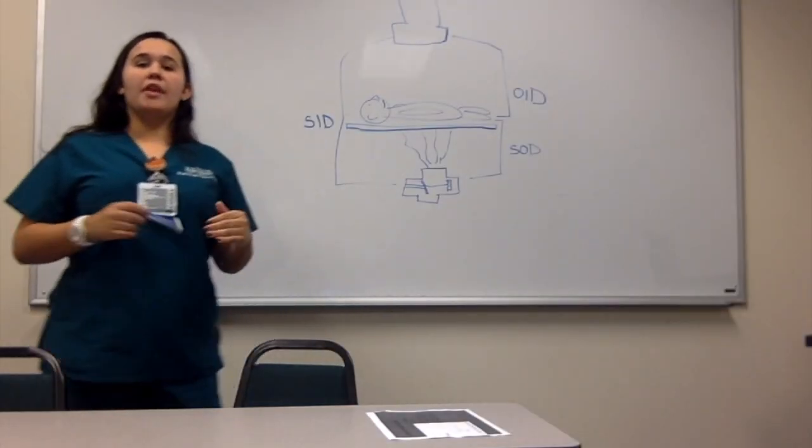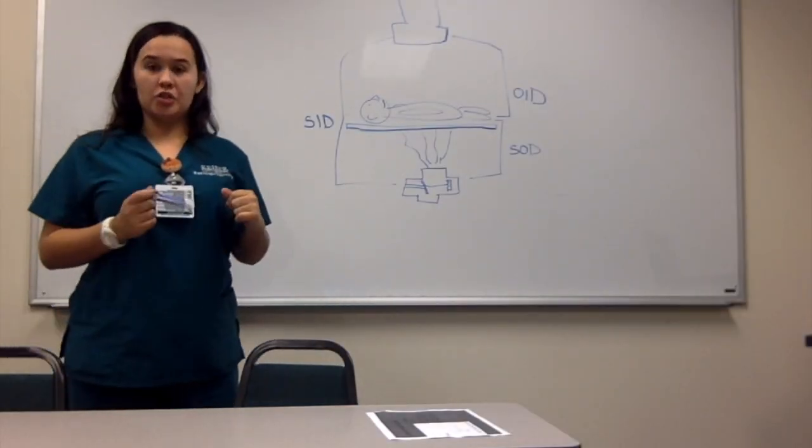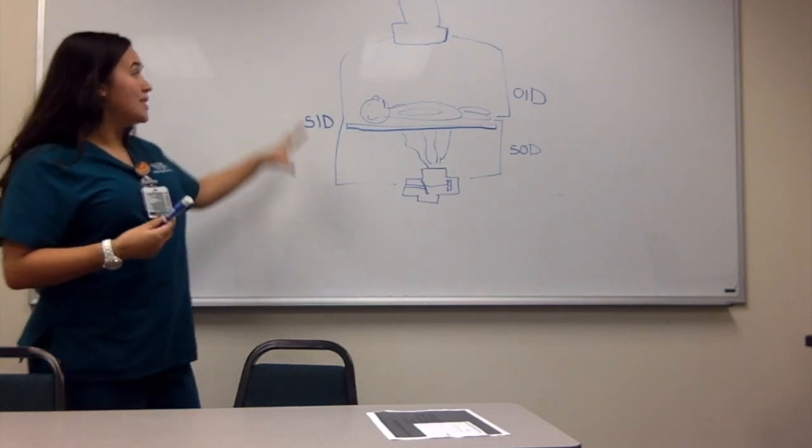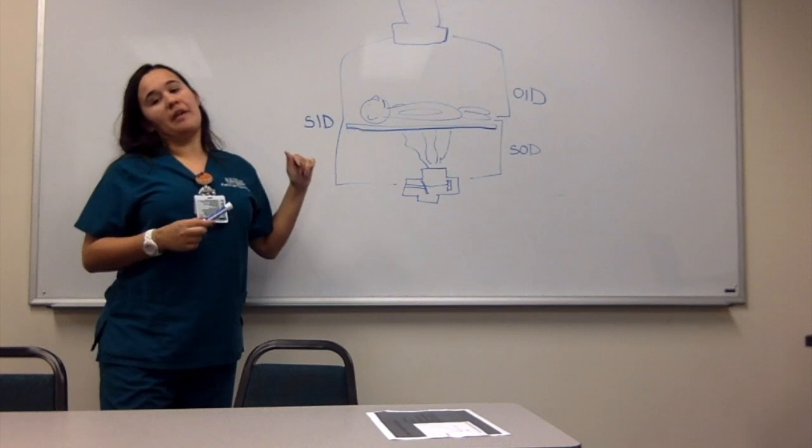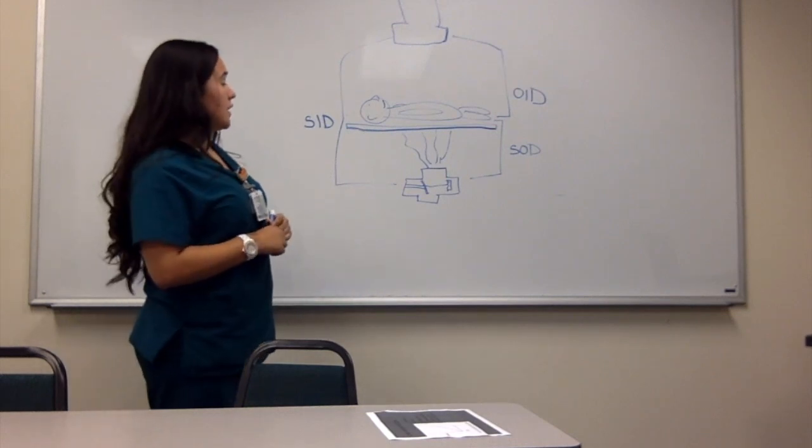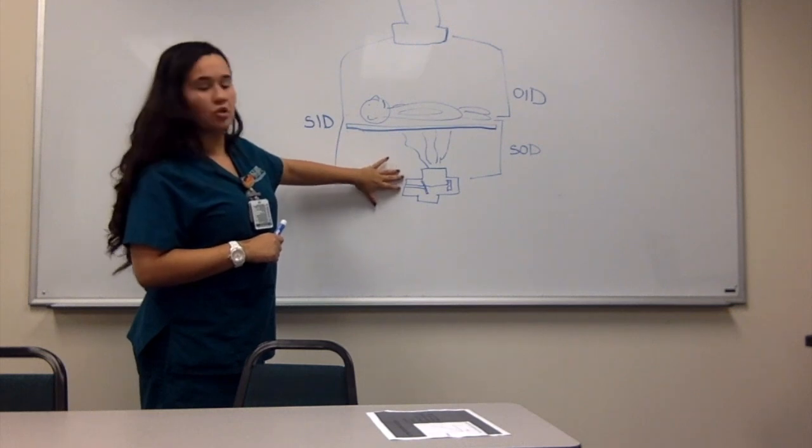So in normal x-ray, the bigger the SID, the less patient dose. But in fluoroscopy, it's a little bit different. When you decrease the SID, you actually have less patient dose. The reason behind this is because the tube is at the bottom in conventional fluoroscopy.